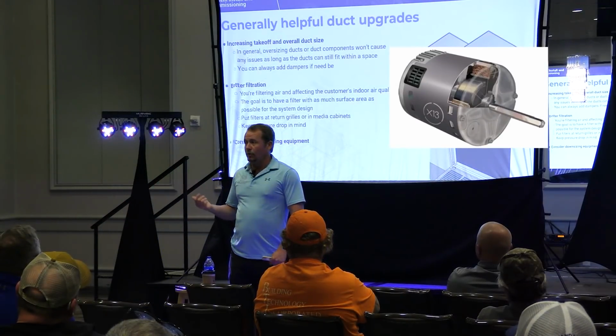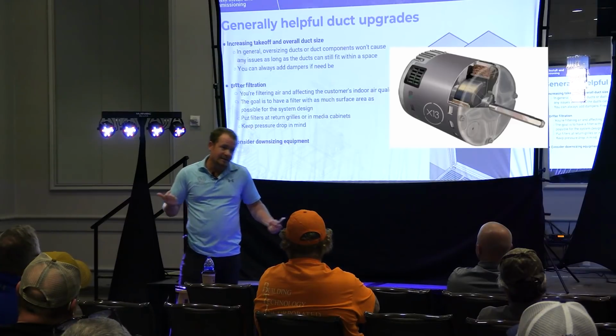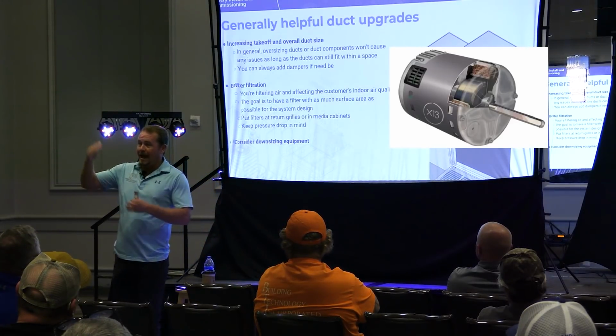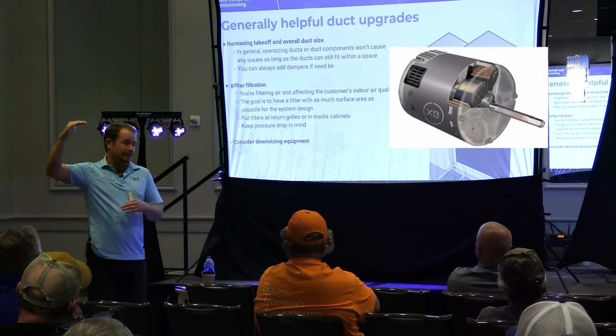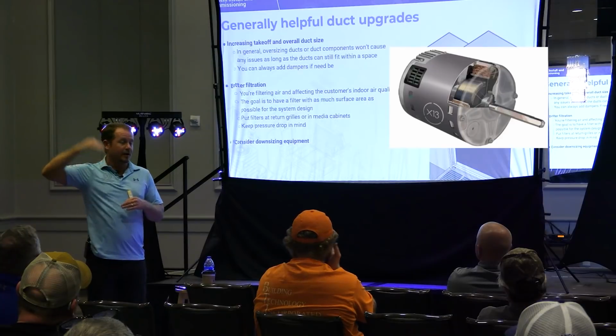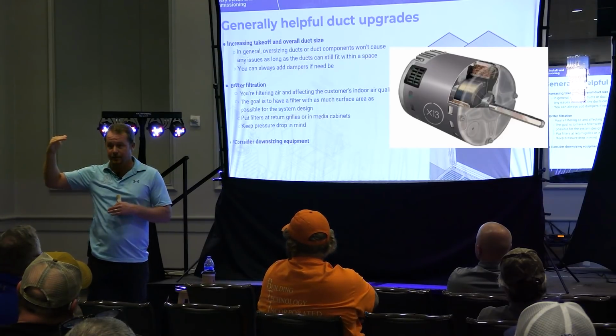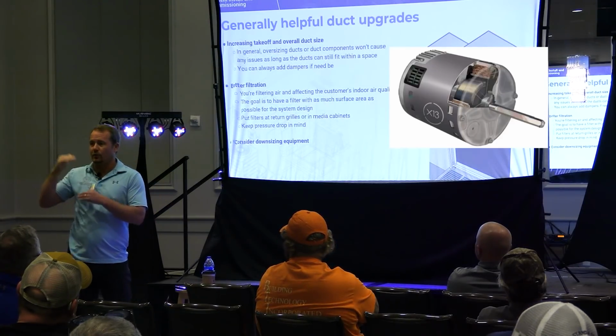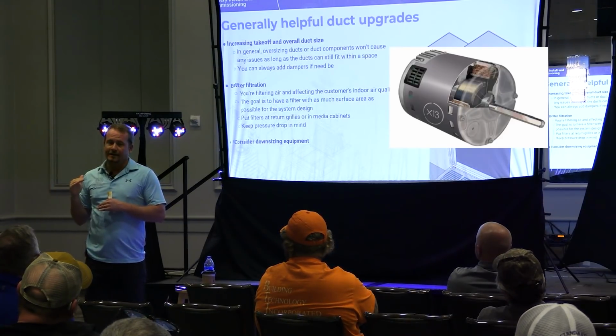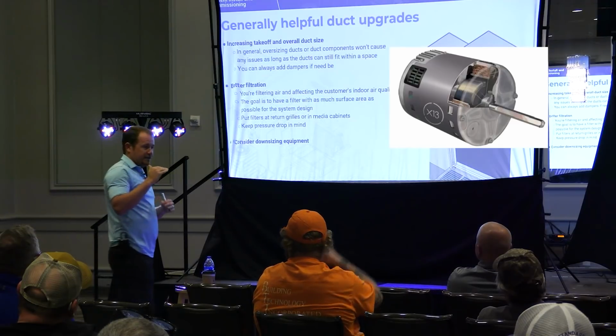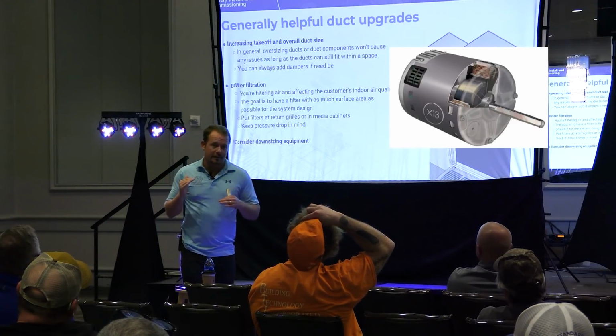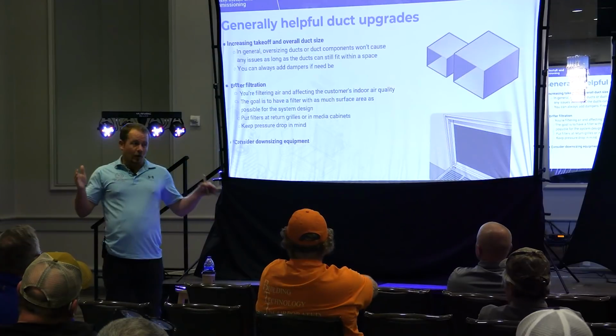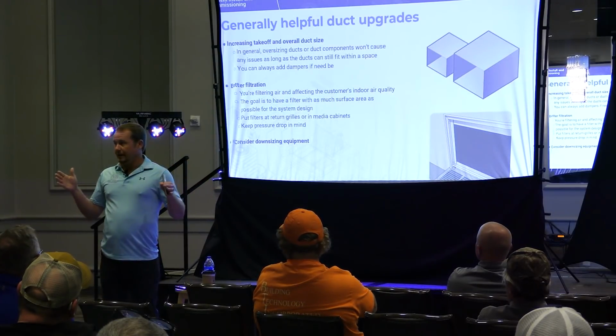The motor, ECM blower motors, X13s, number one reason the things fail is because they're running past their design static pressure, meaning they're having to run faster, meaning they're running hotter than they ever were designed to. They're designed to for short periods of time when the filter gets dirty. They're not designed to run above their stock speed all the time from the moment that they were put in because the ductwork's too small. And then it also increases filtration, meaning it cleans the air better.